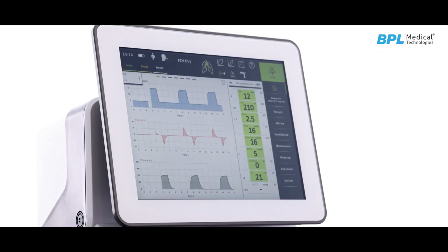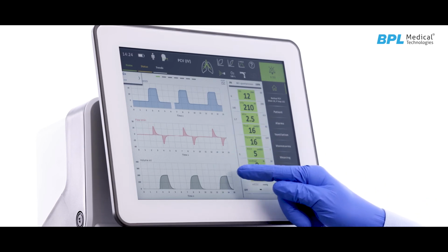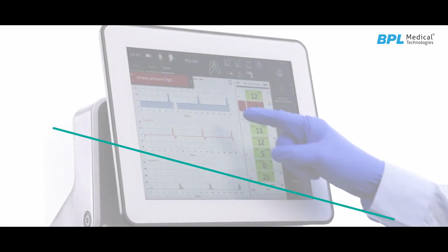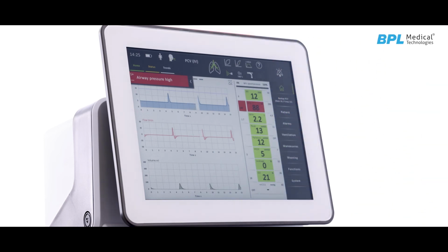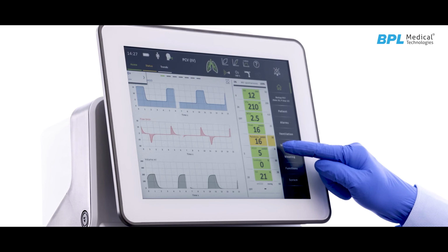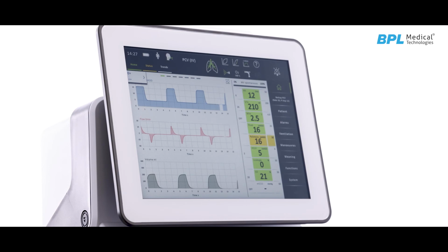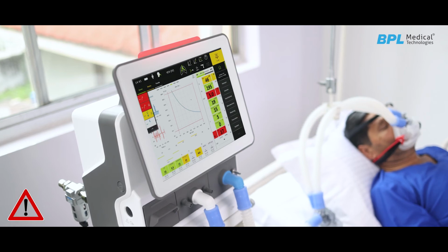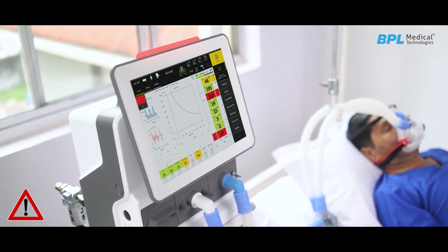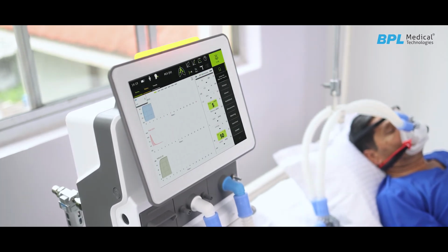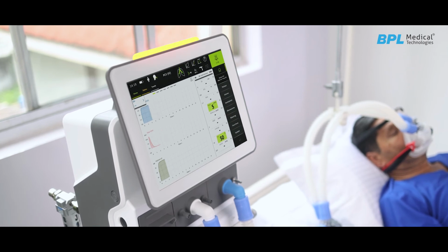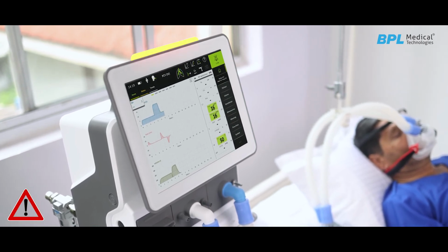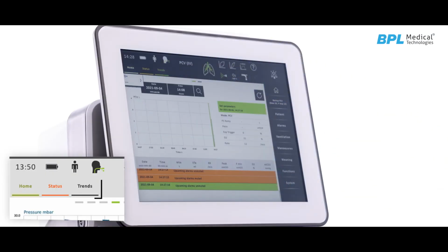ELISA 300 can display up to 4 waveforms simultaneously in different colors. Waveforms are user configurable by long press on the screen. ELISA 300 features visual and audible alarms as per IEC standard. Alarms are categorized into 2 levels: high priority alarms and indicative alarms. They can be differentiated by looking at the alarm lights or messages and hearing the alarm tone. High priority alarms are shown in red color with longer tones so that they immediately capture the user's attention. Indicative alarms are shown in yellow color and have a shorter alarm tone. The eye-catching traffic light on top of the display will alert the clinicians from a distance. By pressing the trend icon, all the recorded alarm trends can be viewed with time and date.